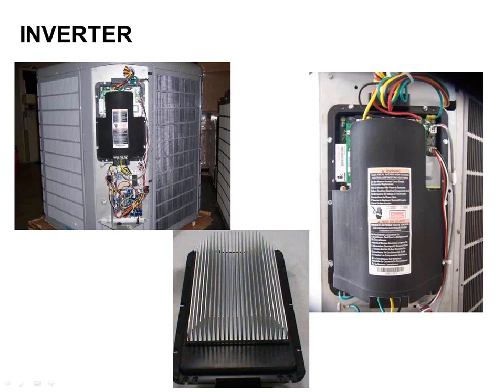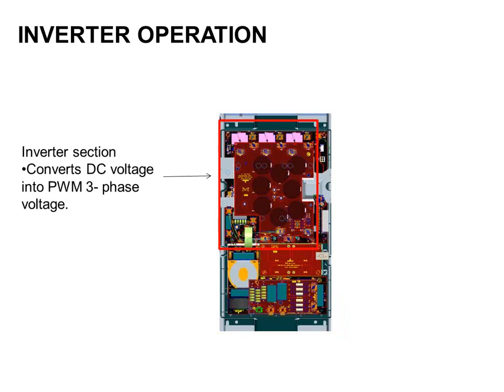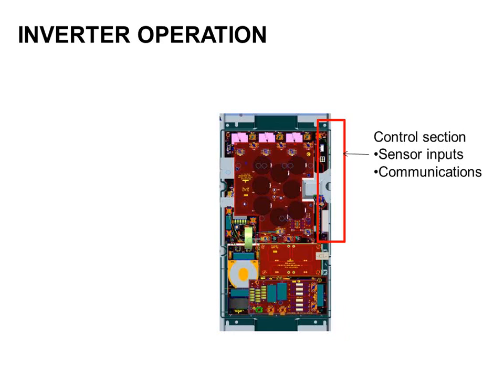There's a converter section to the inverter. The converter's job is to convert the AC power to DC power, because once it's DC, now I can modulate it and play with it. Then the inverter section takes that DC power and converts it to three-phase pulse width modulation and sends that voltage out to my compressor. In this particular case, the compressor is a DC compressor. That is very common. If I had an AC compressor, I'd have to convert it back again.